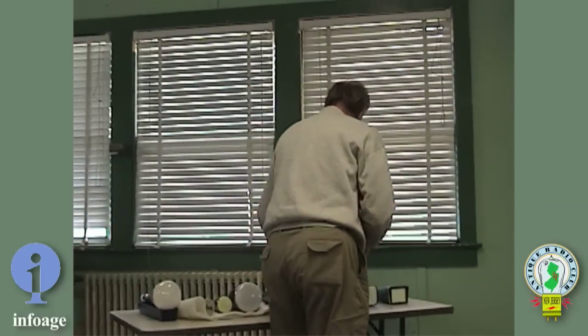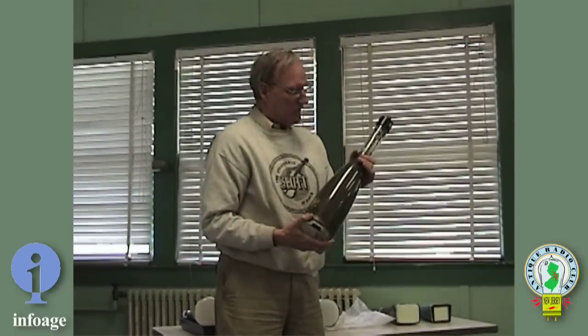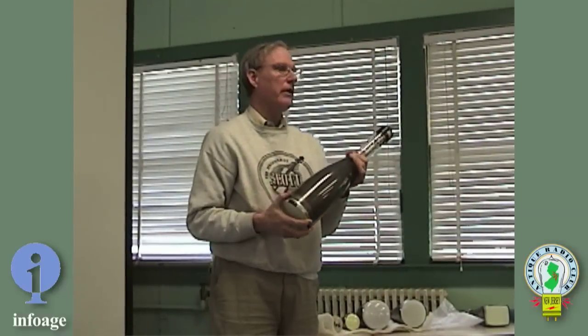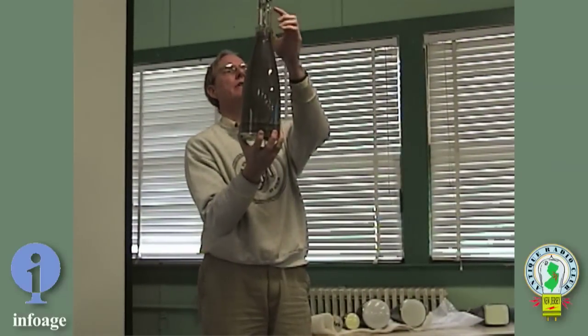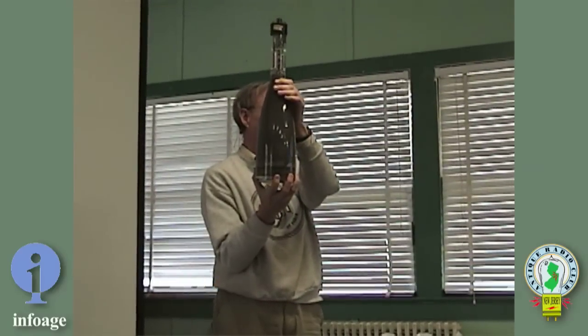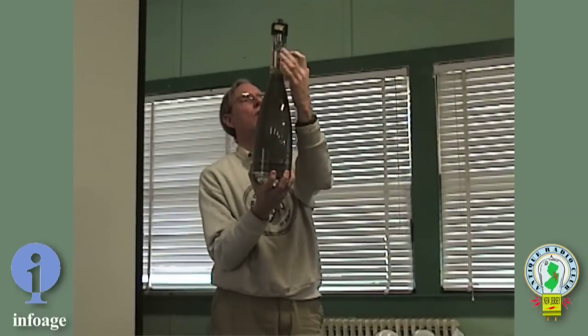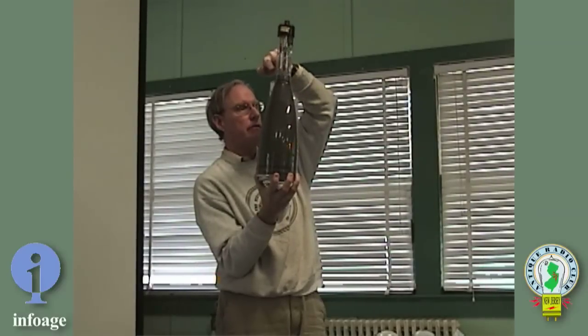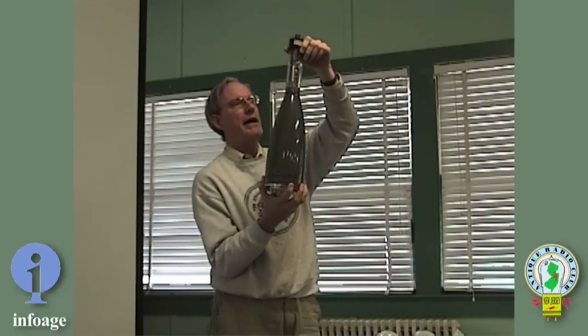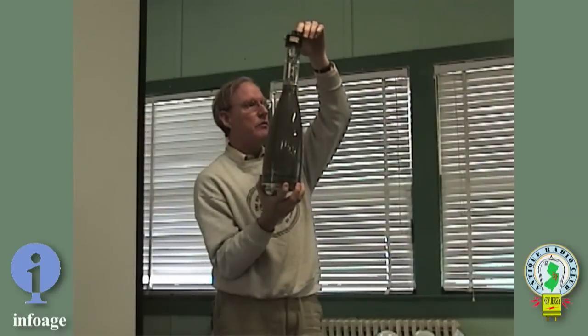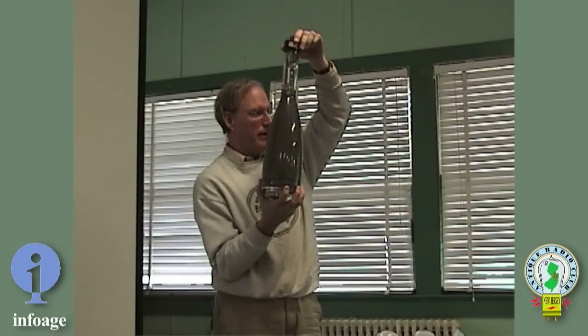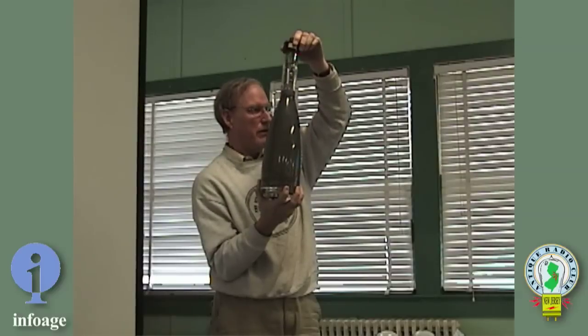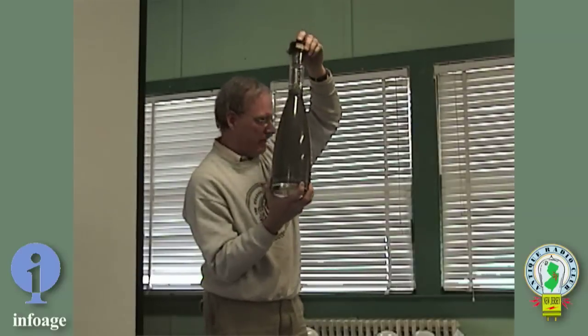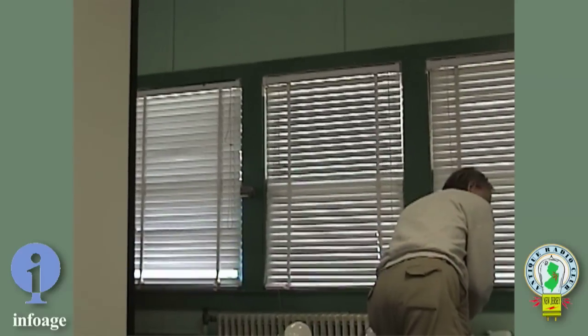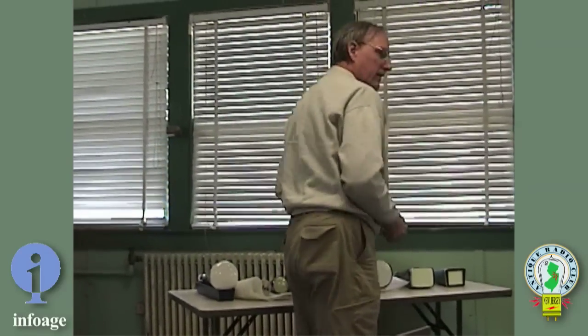And the last breakthrough is actually back in this tube. This breakthrough allowed them to get from 30 megahertz up towards 100 megahertz. And if you look real closely inside this one, you'll see there's a bunch of coils in there. What they've done is they've actually cut the deflection plate up into sections and then provided a coil, a little matching network from one plate to the next, to the next, to the next. The purpose of this is to match the velocity of propagation down this structure to be the same as the beam of electrons that's passing through it. And the result is they get the best and flattest deflection sensitivity all the way out to 100 megahertz. This technology is still in use, even in the most modern ones, the CRT. So that's kind of how it went until LCDs knocked everything out of the market.